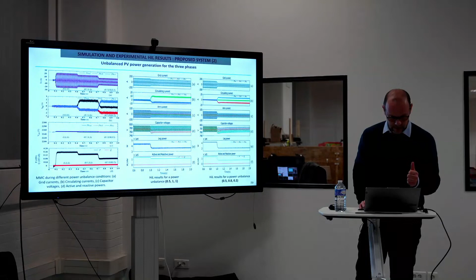That's how centralized systems work—for example, in terms of efficiency losses, because one central unit controls everything, which is impossible to control well. There's low voltage rating of the PV due to safety issues, and a lack of modularity. That's a major problem—one of the main issues is the limitation of switching power ratings, since a switch can only handle a certain amount of voltage and current. If I want to increase further, I cannot.